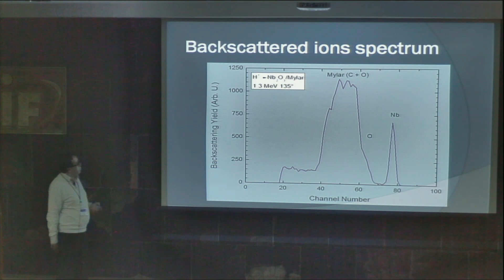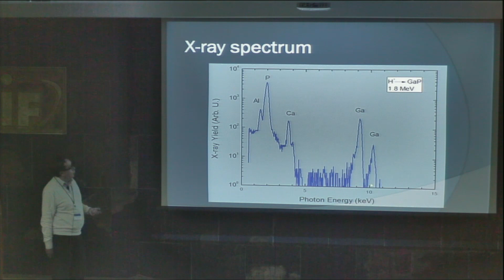And this is an example of a gallium phosphide standard. Here we have the gallium K alpha and K beta peaks. We have the phosphorus K alpha and K beta peaks. It is impossible to resolve the K alpha and K beta. We have a spurious signal from aluminum. And we have seen that mylar substrates are always contaminated with calcium, so this is also useful to calibrate the energy of the spectrum. You can see we can integrate these peaks fairly easily.